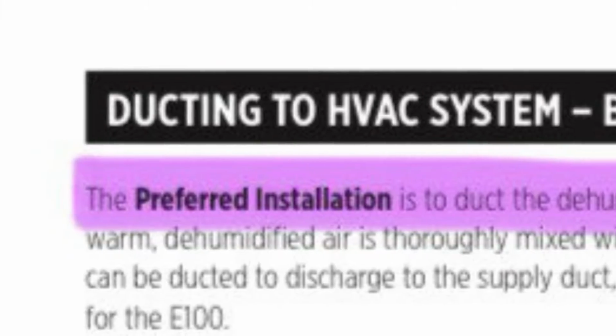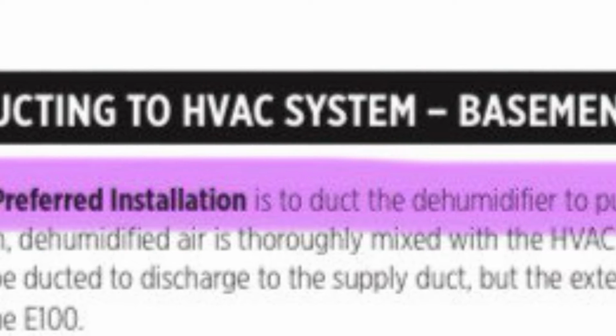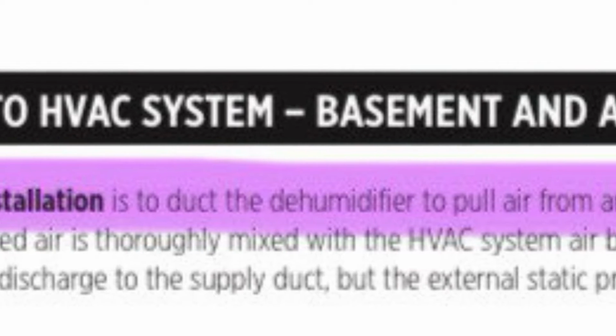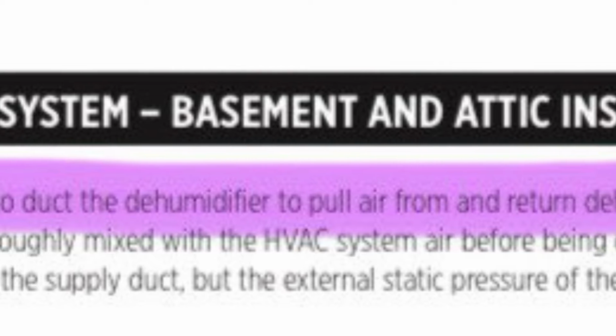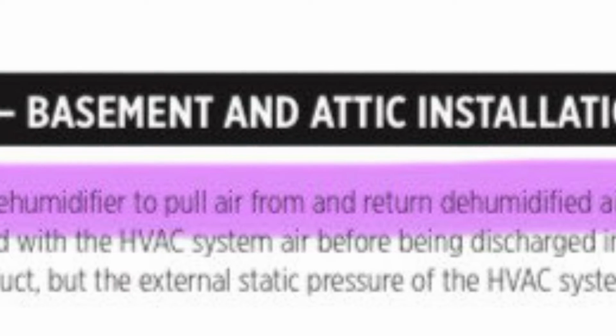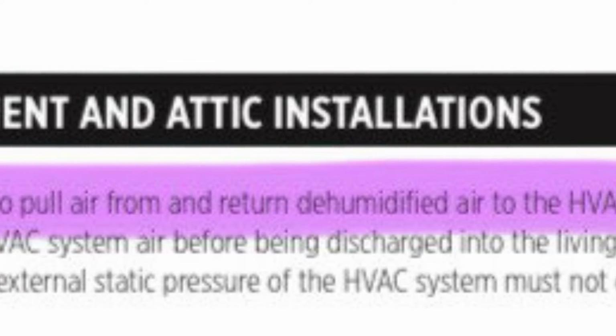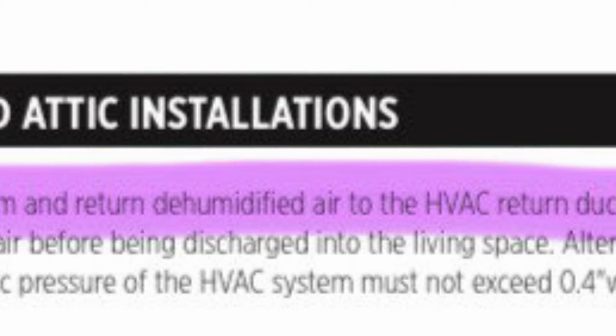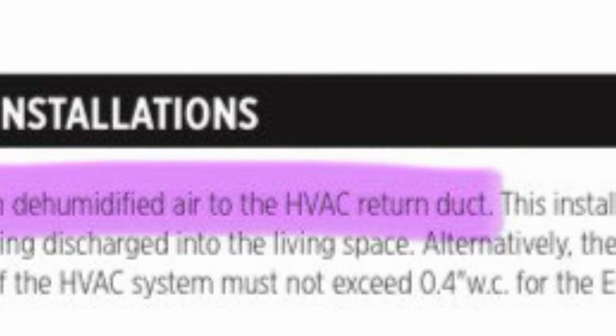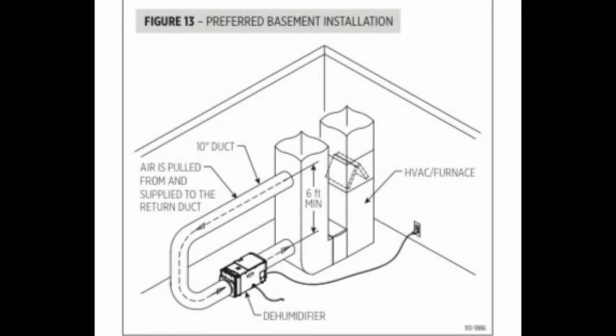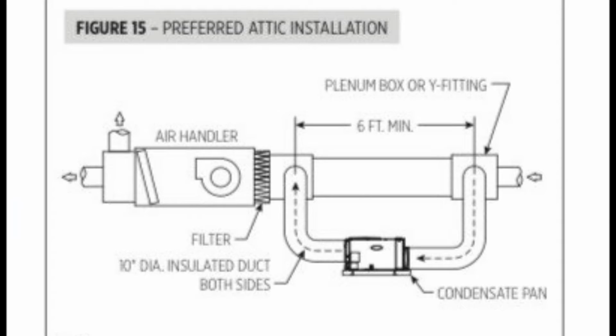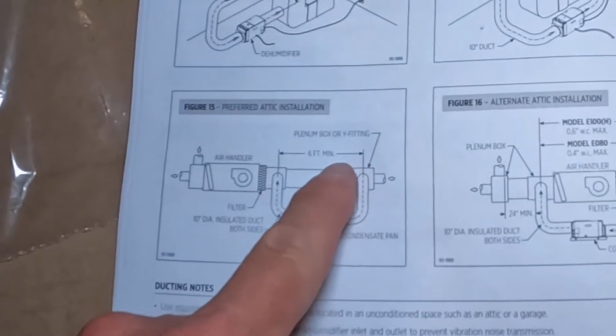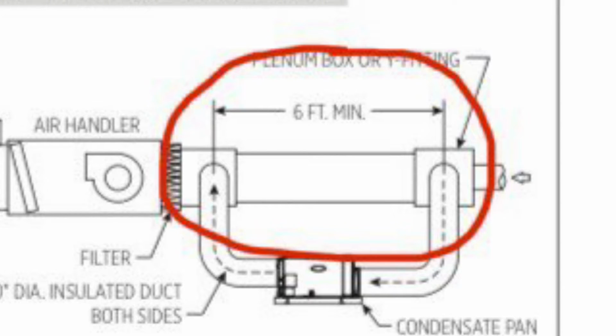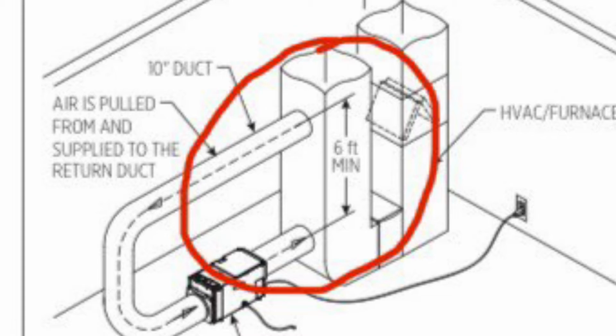If you look at page 10, it shows the preferred installation is to duct the dehumidifier to pull air from and return dehumidified air to the HVAC return duct. There are a couple pictures here - this is the basement installation and this is the attic installation. Make note of this, 6 foot minimum.